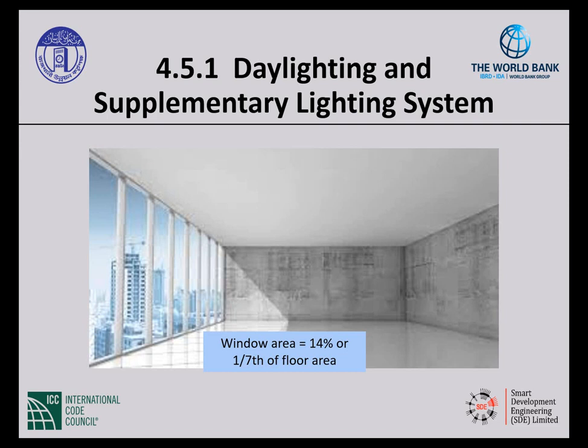So if I have 14% of my floor area, that equates to my window area, right? So that's what that's trying to tell us. Now, it also goes on in 4.5.1.2 to tell us that every regularly occupied space, that's again a defined term, so you can look that up, shall contain a minimum percentage of daylit area along the building perimeter. And so we have no window less than 1 meter square to ensure that that light can come in, so that we can comply with the rest of the provisions that we're getting ready to talk about.